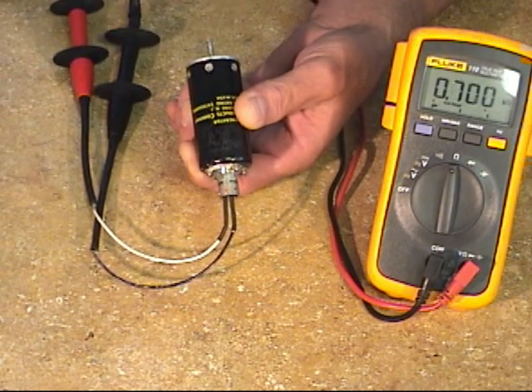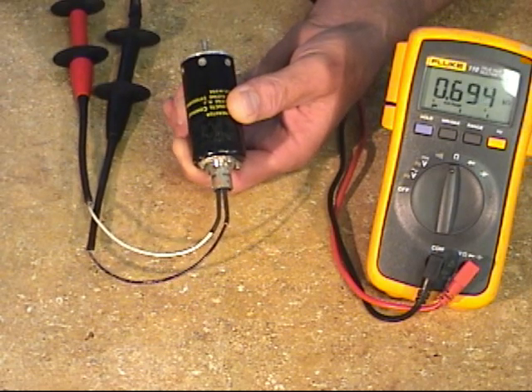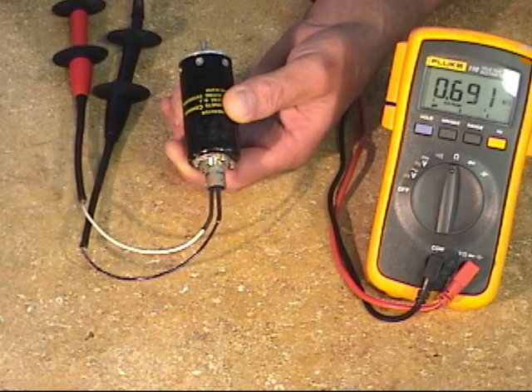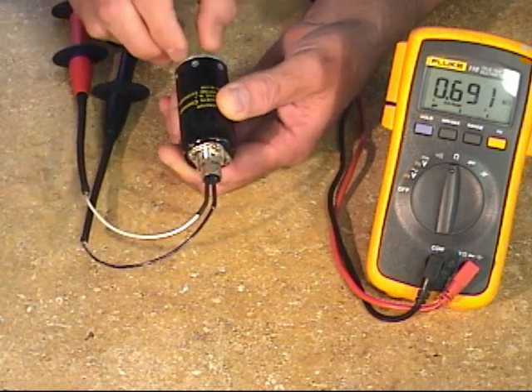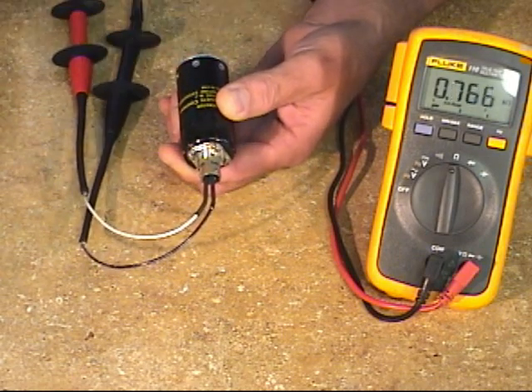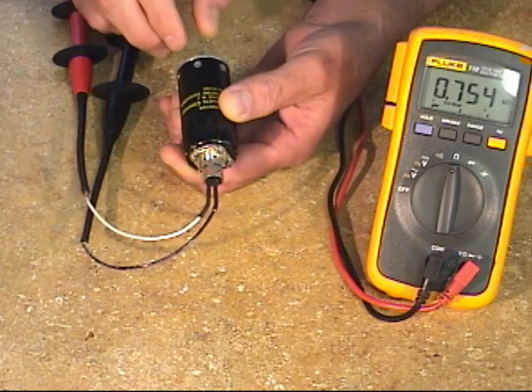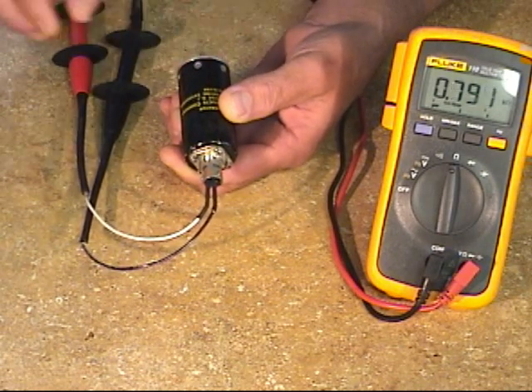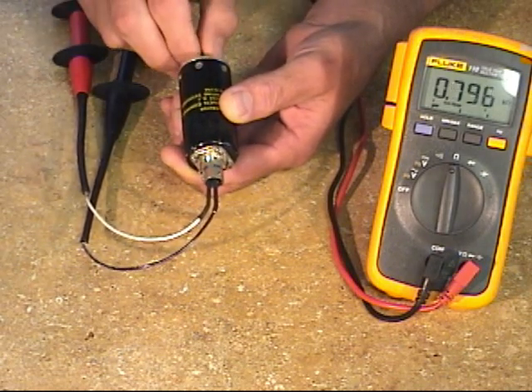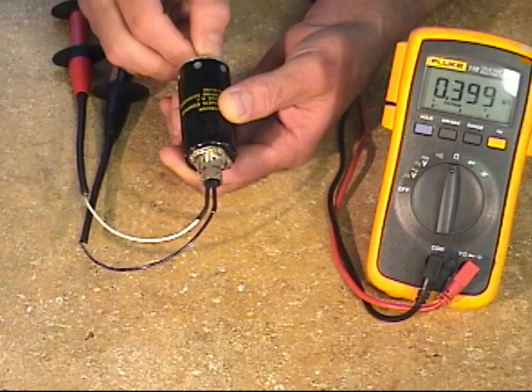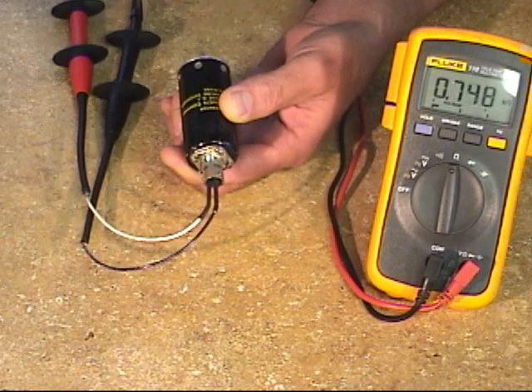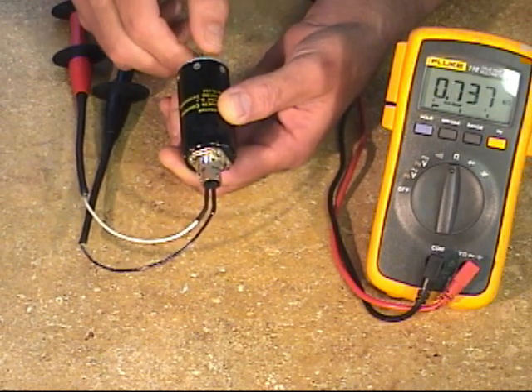Other thing you might do. Tap on that shaft a little bit. This one's not too good. This one's a little bit high resistance right here. So we'd go a tenth of a turn at a time, and we'd log it in. Looks like we saw an 8, something in the middle, 830 or 850 there. Now don't worry about the numbers while you're turning the shaft. Of course the meter will just be erratic.